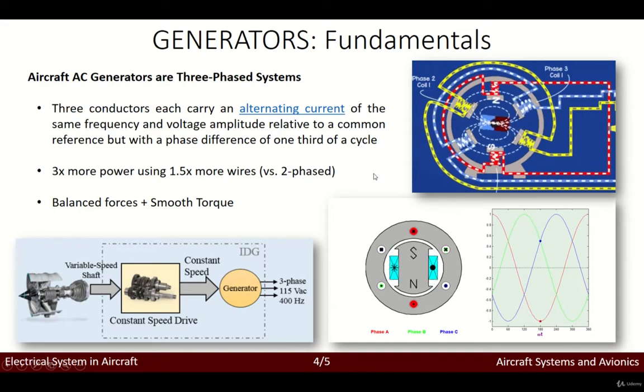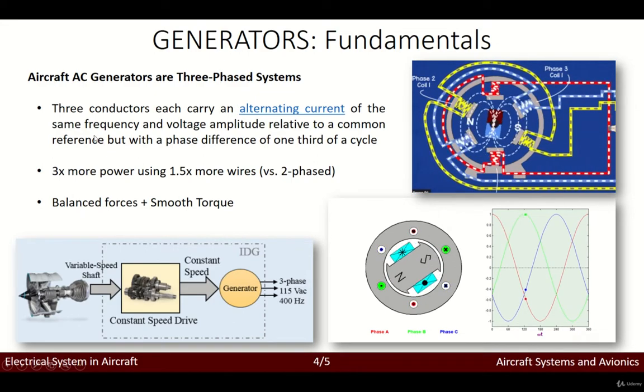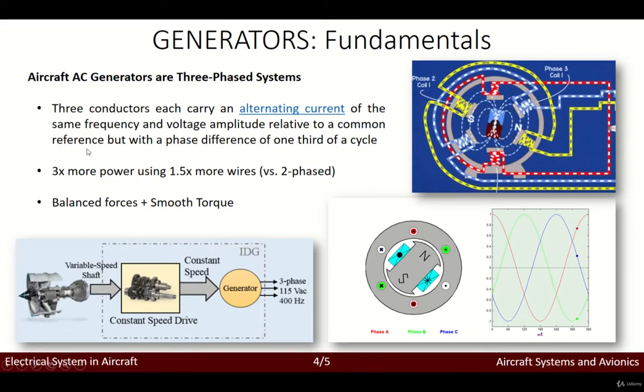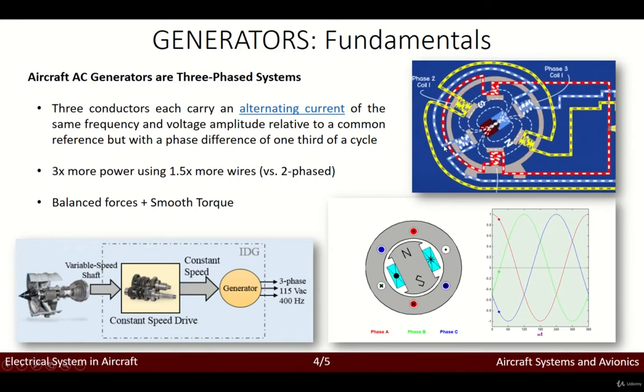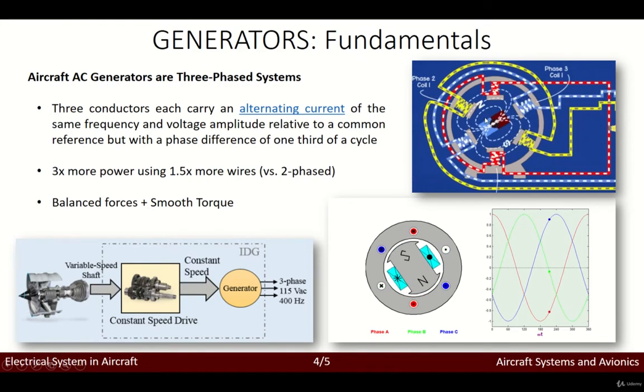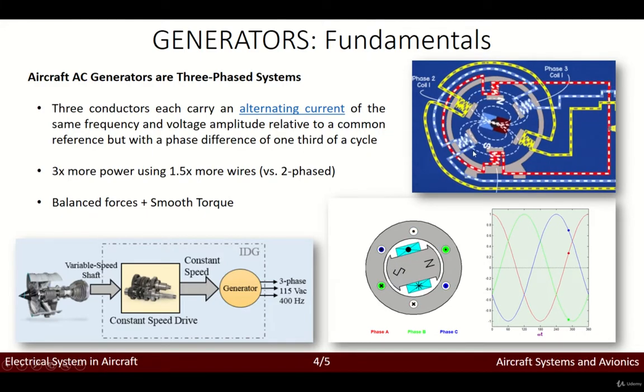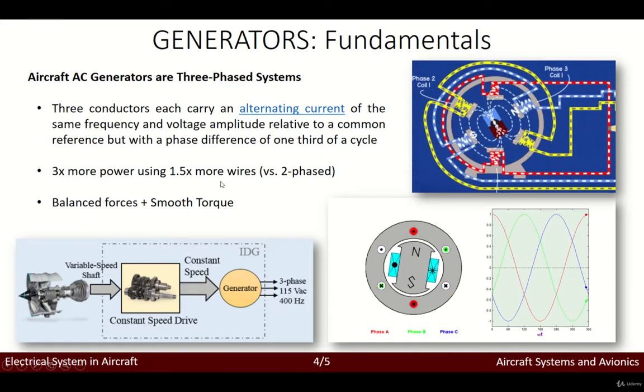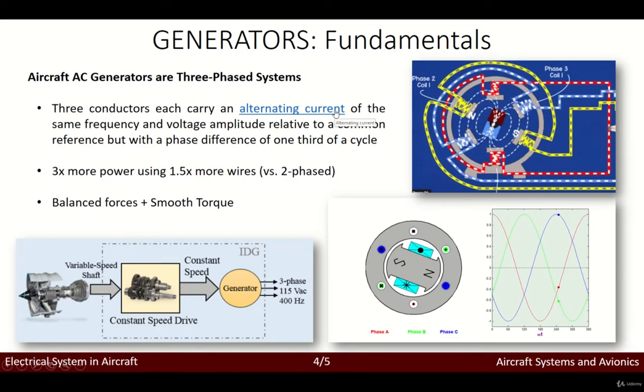So what are the fundamentals of generators? First of all, we need to understand that our generator will be based on a three-phase system. The three conductors will each carry an alternating current of the same frequency and voltage amplitude relative to a common reference, but with a phase difference of one third of a cycle. This phase difference means that the geometry of our generator will be clearly divided into three main axes — three coils. By using three phases, what we get is three times more power using only 1.5 times more wires, compared to a two-phase version.